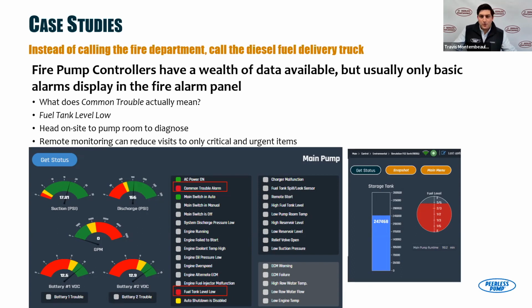When I get in tomorrow morning, I'll place a work order for diesel fuel delivery, and that will clear that common trouble alarm effectively. So the goal is that we're trying to reduce visits to critical and urgent items. And if you think about this from a servicing contractor perspective, hey, I've got a common trouble alarm. There's something wrong with my pump. I don't know what the deal is. First thing you have to do is roll out there, assess what the situation is, and then you come up with a plan to fix it.